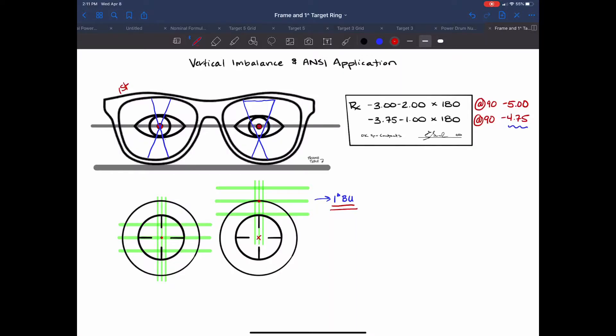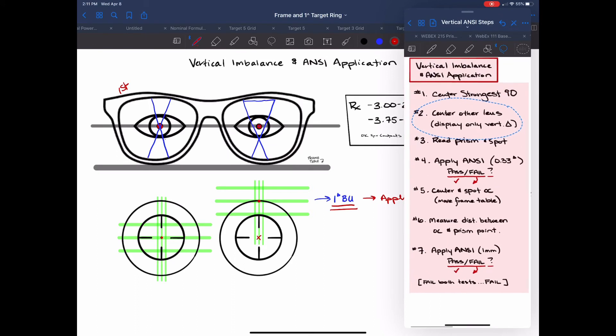So now once we know that we have one diopter base up prism we're going to apply that to ANSI and ANSI allows us how much? 0.33 diopters in any direction but I have one diopter base up prism that's going to fail. So that doesn't pass but we still have one more area of tolerance that ANSI allows us.